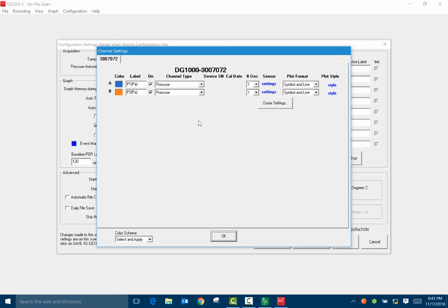And we're going to actually do a CAZ test where we'll be monitoring the house to outside pressure and the vent to outside pressure, and we'll see how those pressures, both those pressures, change as we start turning on exhaust fans. So I'll go through a series where I'll turn on 4 fans, a clothes dryer and 3 fans, and then turn them off, and then we'll look at the results.